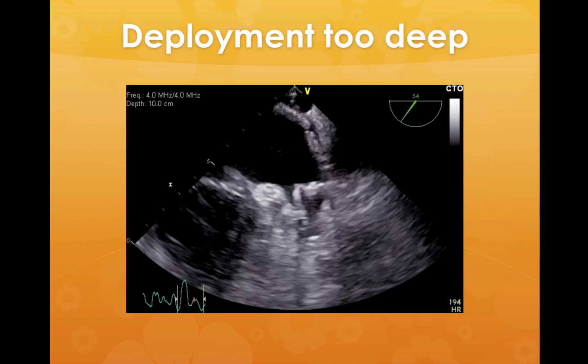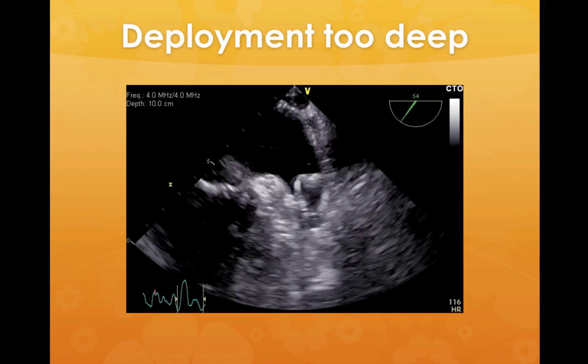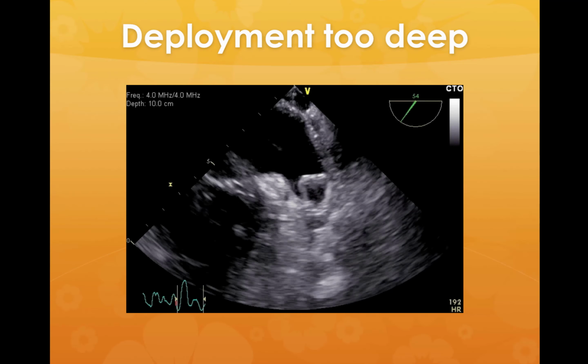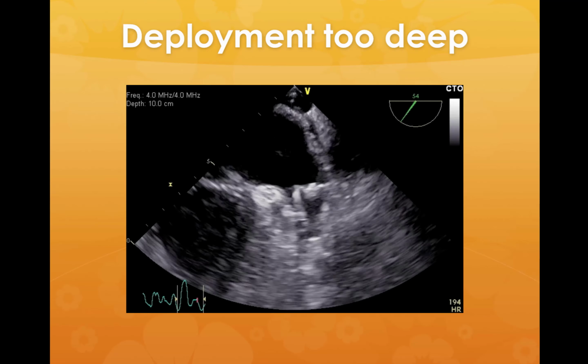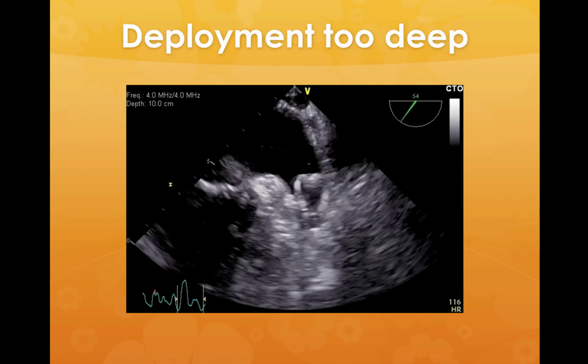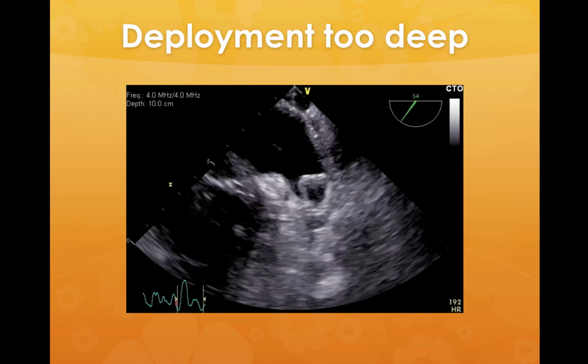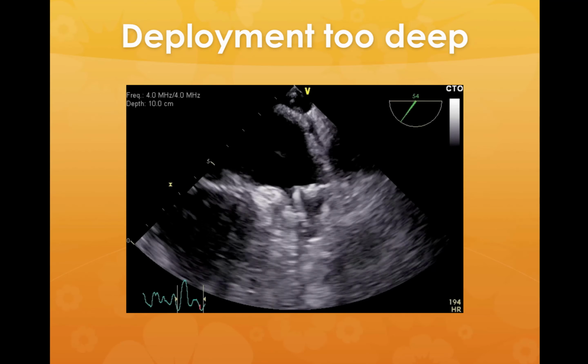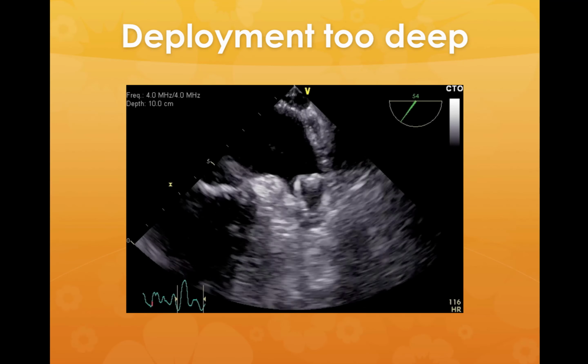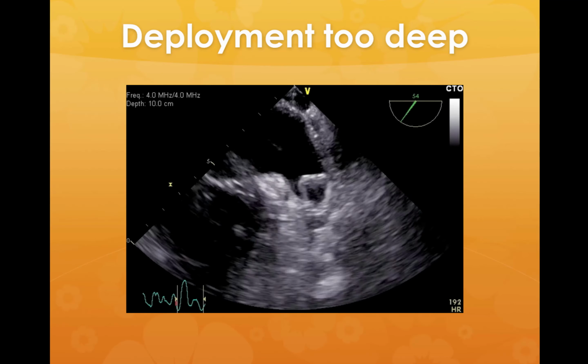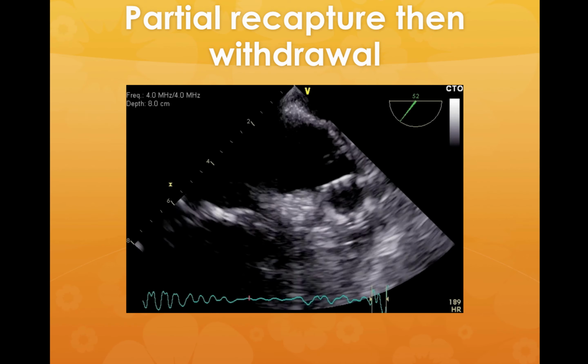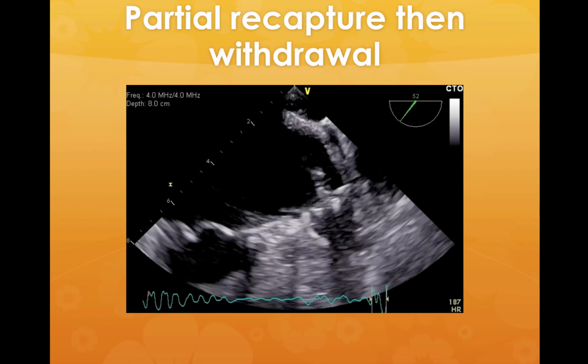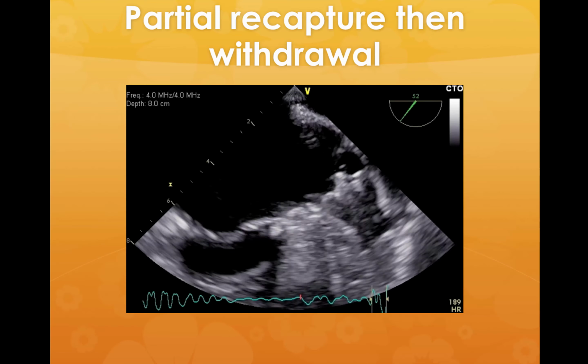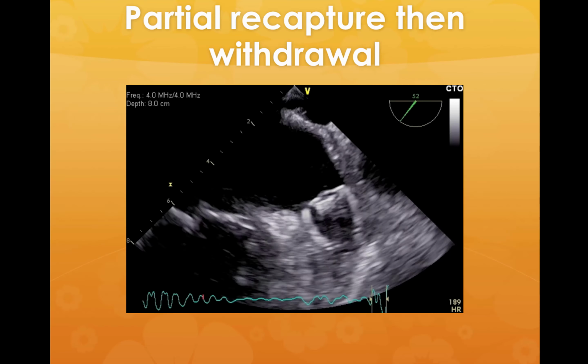And then the things we really want to know once it's deployed is, has it opened properly? Is there a gap around the outside of it? Is there colour flow around it? And then also, how big is it? Because we want it to be compressed by about 8 to 20% of the size. So if it's a 30 millimetre device, you don't want to be measuring 30. You want it to be, say, 25 once it's deployed, so you know it's pushing out against the appendage and it's not going to fall out.